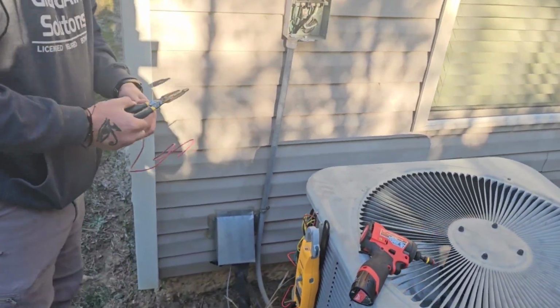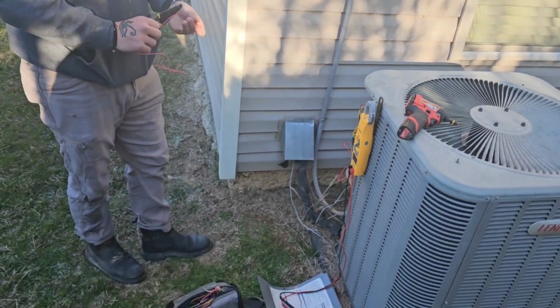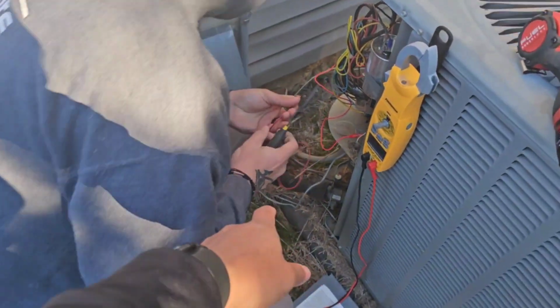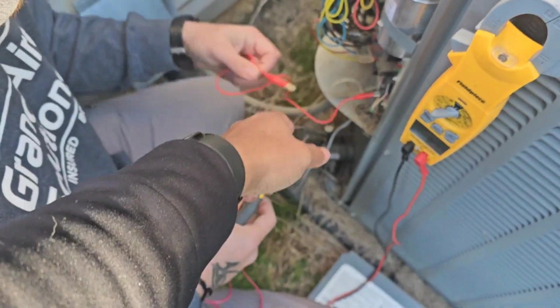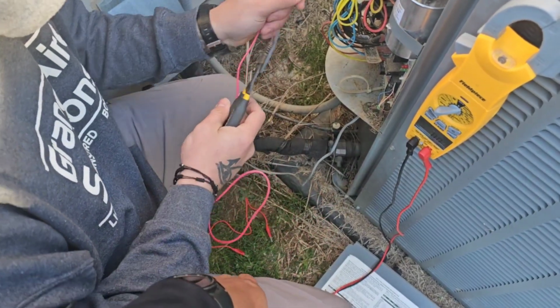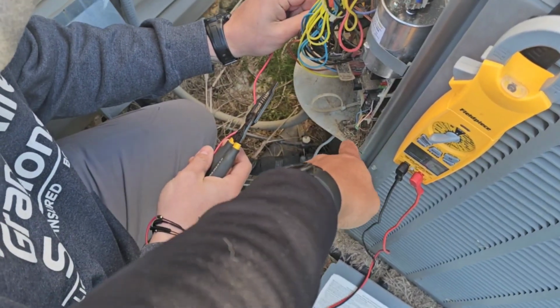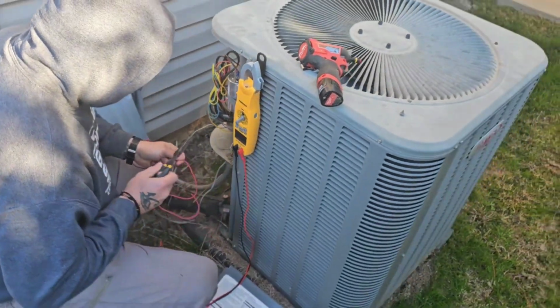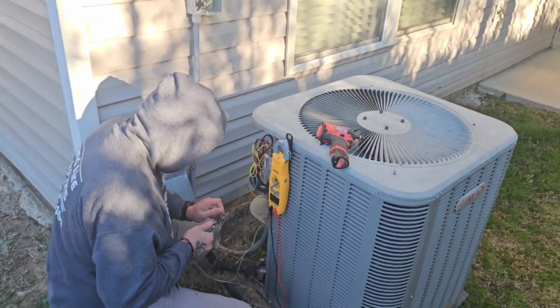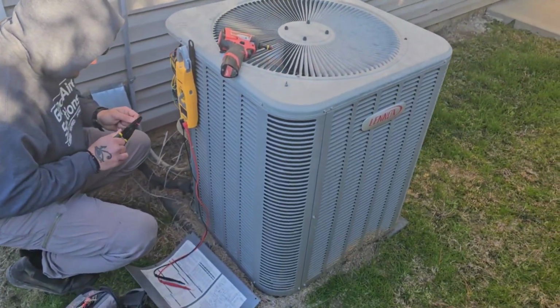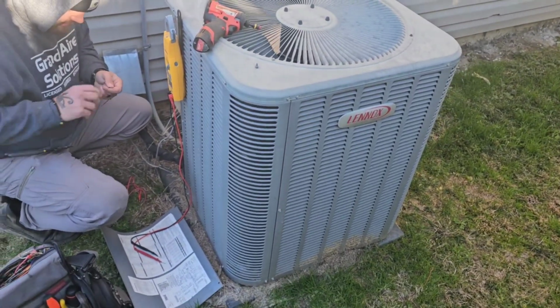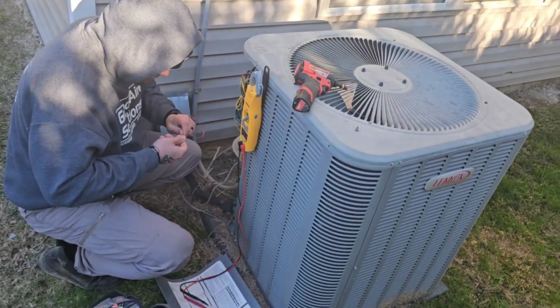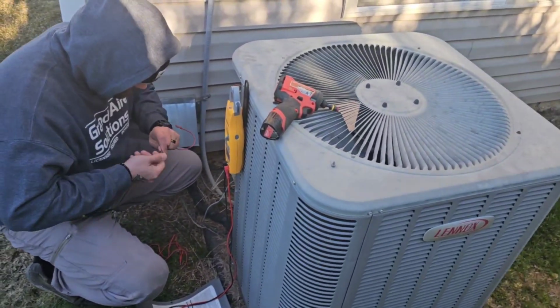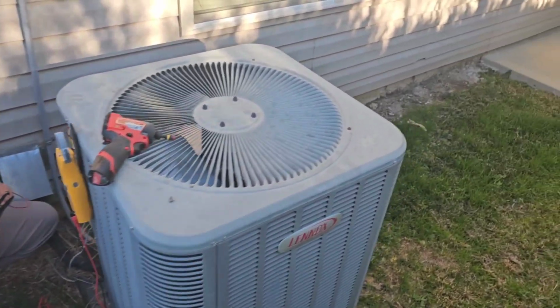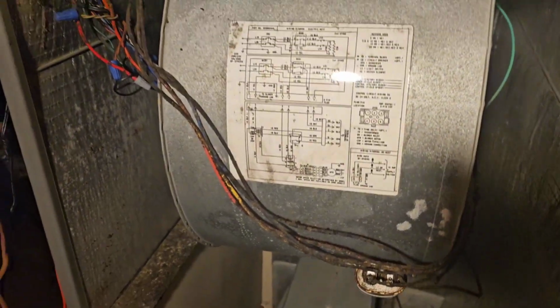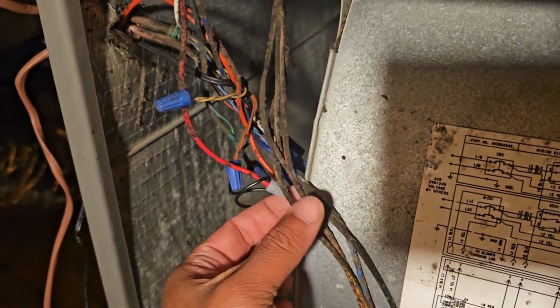And I'm gonna go get the Fieldpiece probes up so we can... So the other side where the jumper is? Yeah, you're just replacing that jumper with the wire in your hand. Yep, put it there. Strip the end and put it in the Y1, and that's how we're gonna get these people heat in case they got somebody moving in lately, because trying to get a Lennox part around here, nobody really wants to drive all the way out to Columbia right now, so we're just gonna have it ordered to the shop and go from there. So let me go get my probes up in the duct. They say the lack of maintenance can really be shown in a system the moment you take the door off.